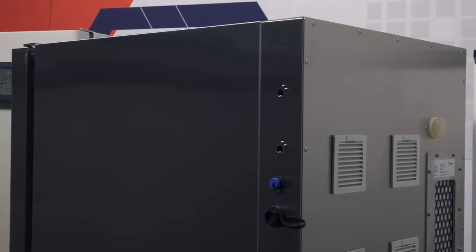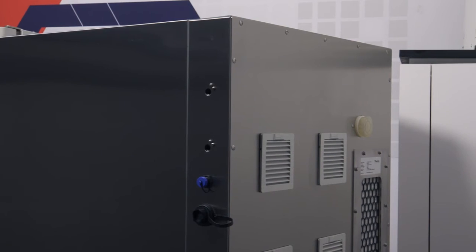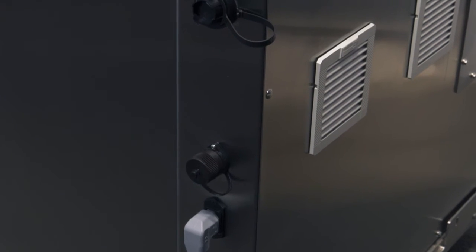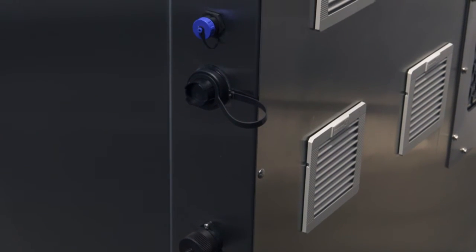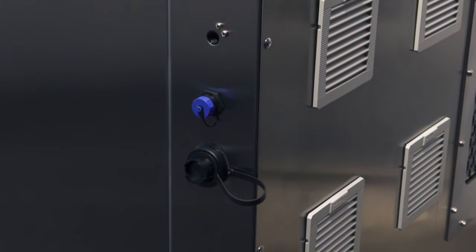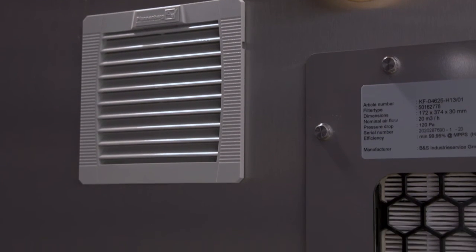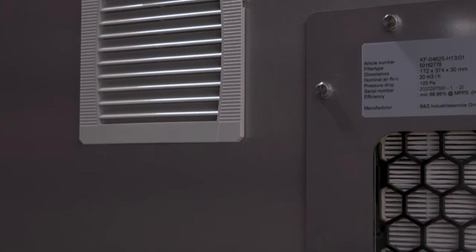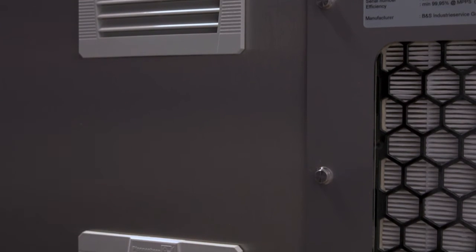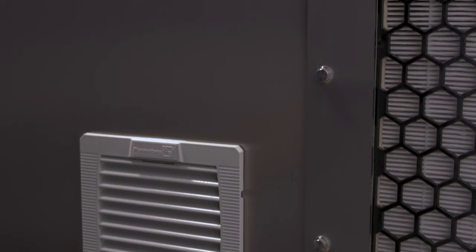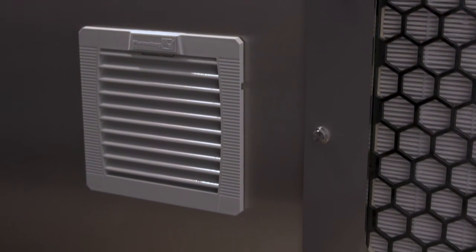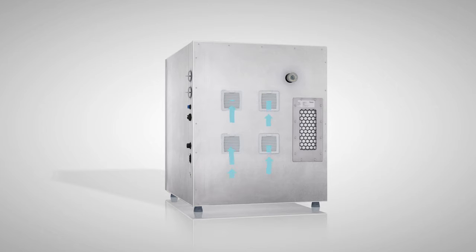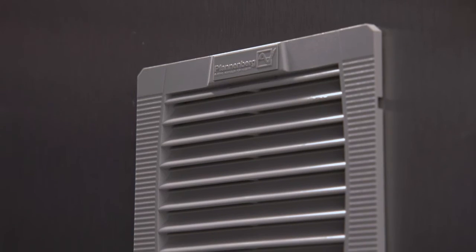So on the back of the unit here, you can see completely enclosed electronics. So a little bit different than what you'd see on a typical CO2 incubator. We've enclosed everything in a stainless steel case. As such, we've added these four inlet filters on the back of the unit, and these are actually pulling air in to help cool the electronics and keep them cool as the unit's running and we've now enclosed this space.